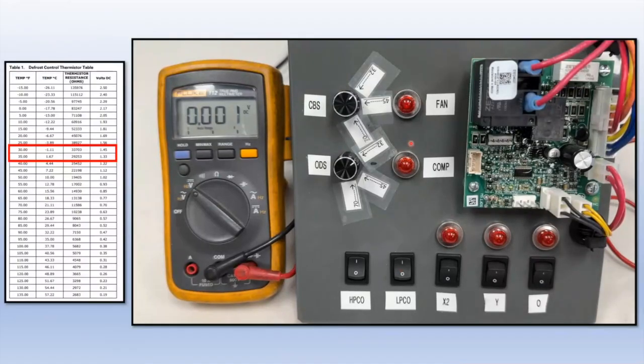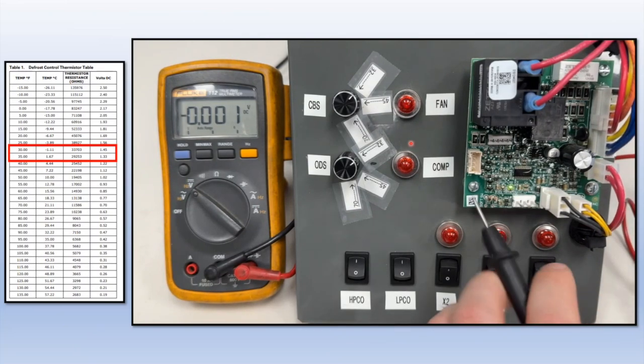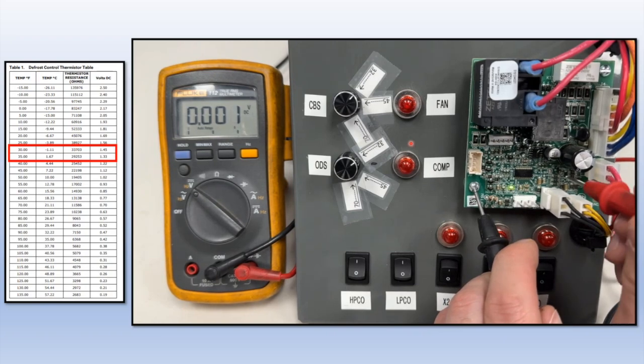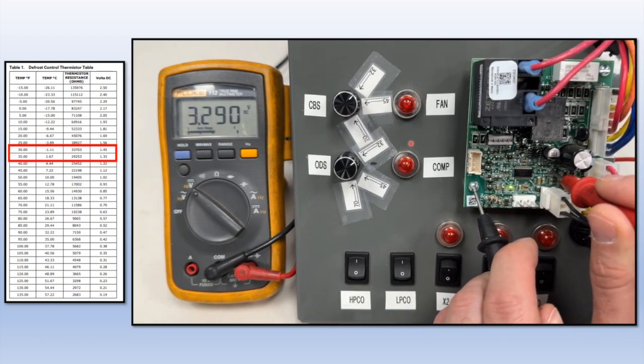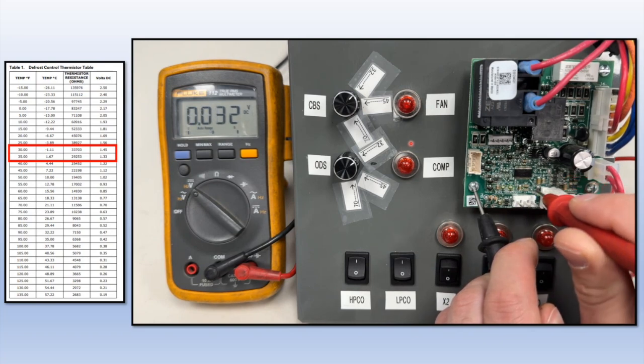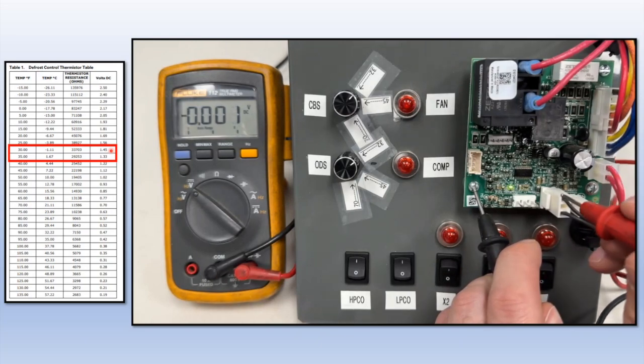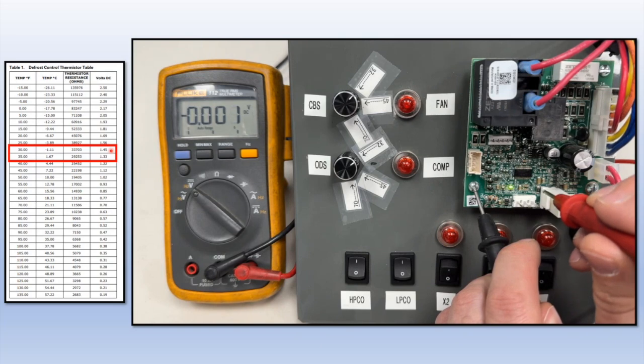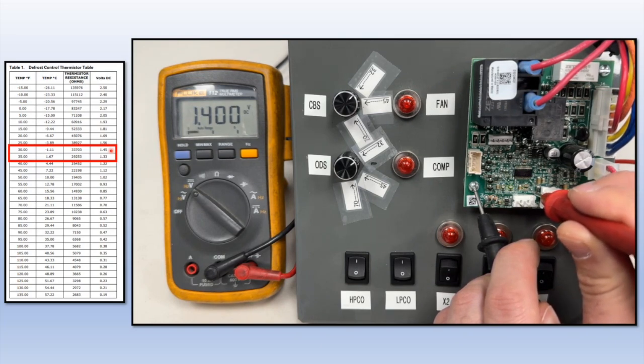If we want to check our voltages, the first thing we're going to want to do is set our meter to volts DC. Put one side on ground, and you can check your source voltage at the 3.3 volt test pad. We verified we have 3.3 volts DC, which is our source voltage going to the sensors. Then we can move to the coil temp test pad. We're seeing 1.4 volts DC, which is roughly 32 Fahrenheit, because in your case, you're going to have these sensors submerged in ice water. In my case, I just have it set to 32 because it's a rheostat. And then you've got the outdoor ambient temperature. It's also at 1.4 volts DC.